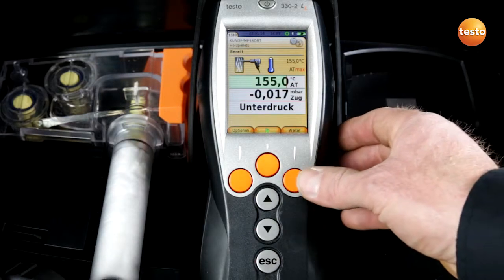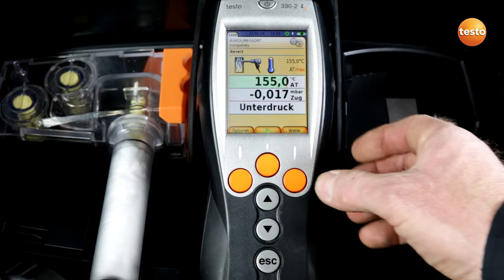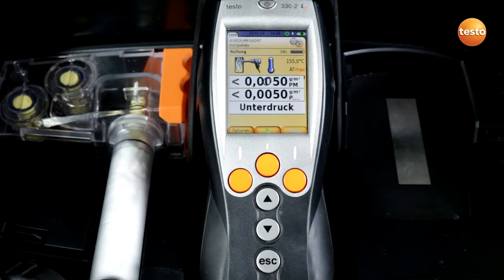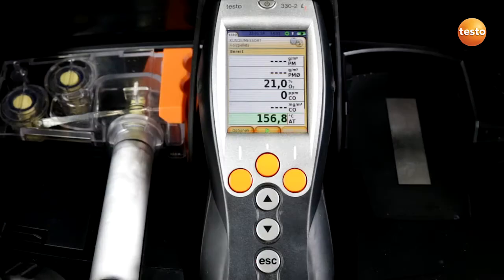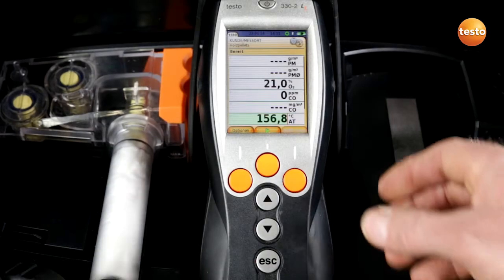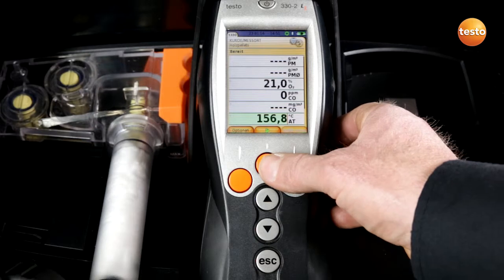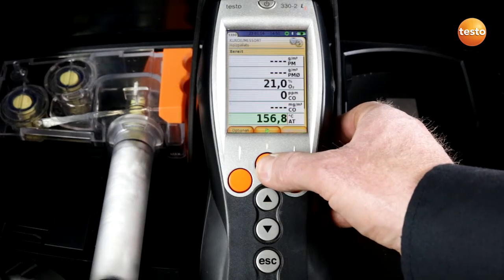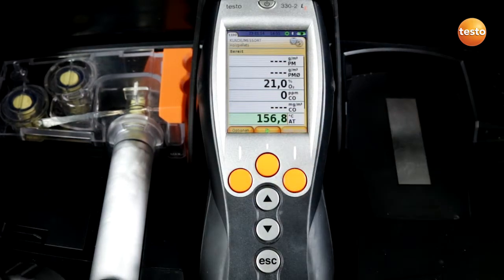I go to Continue with the button and the measuring instrument begins zeroing. After zeroing is finished, the measuring instrument is ready. I confirm by pressing the green arrow button. A stabilization phase runs lasting 3 minutes. After this stabilization phase, the 15-minute regulation measurement automatically begins.